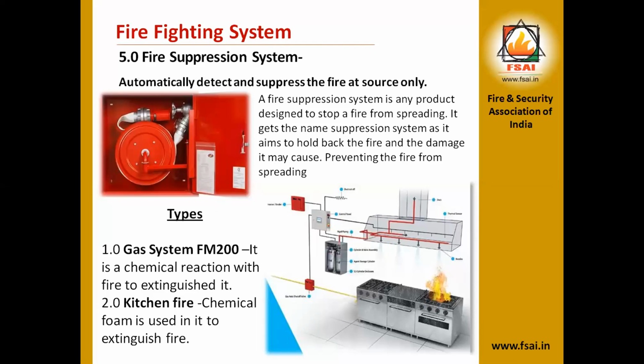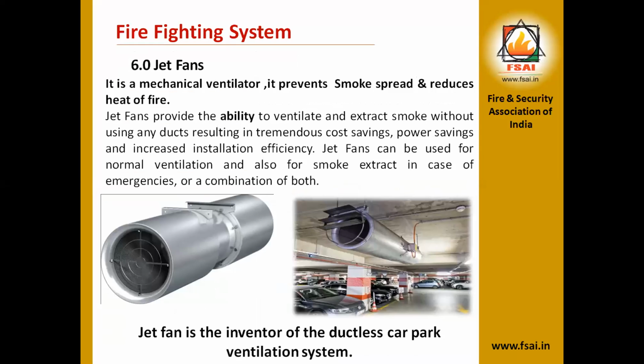Next is jet fans. A jet fan is a mechanical ventilator. It prevents smoke spread and reduces the heat of fire. So jet fans provide the ability to ventilate and extract smoke without any duct, resulting in tremendous cost saving, power saving, and increased installation efficiency. This means that jet fans directly save cost for the builder or any person who is constructing the building, because there is no need to provide separate ducts or to maintain the ducts. It can be used in the car parking area also.